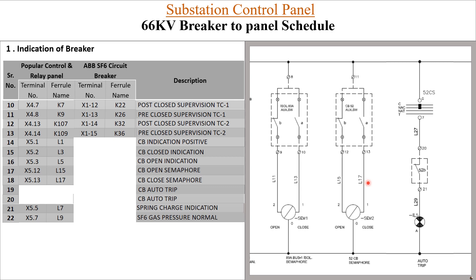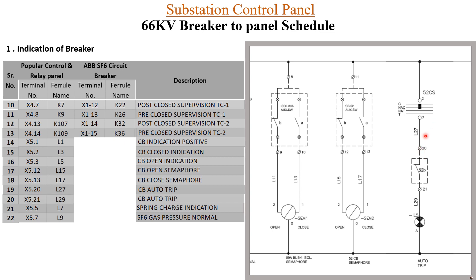For CB auto trip, the wiring is done through the TNC switch. Whenever the CB is in open condition, a normally-closed contact of the auxiliary switch provides the CB auto trip indication. Terminal X5-20 with ferrule L27 is used, and the return comes from X5-21 with ferrule L29.